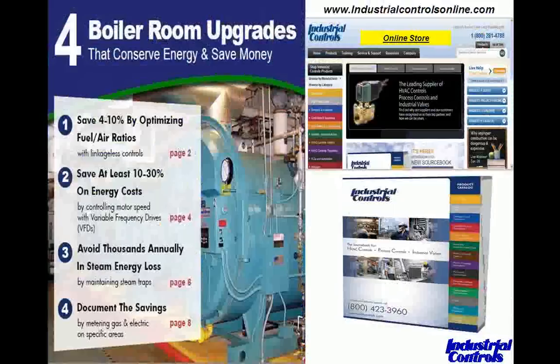We cover four categories in this boiler room upgrade brochure: optimizing your boilers, linkage-less controls, and VFDs. We did a webinar last week on VFDs. In fact, I'm doing a job myself right now where we're upgrading controls on a 1,400 horsepower boiler to make it more efficient and save gas usage. By putting a VFD on the fan motor, we saved even more energy and money than the controls upgrade alone — we kind of doubled our savings on that job.